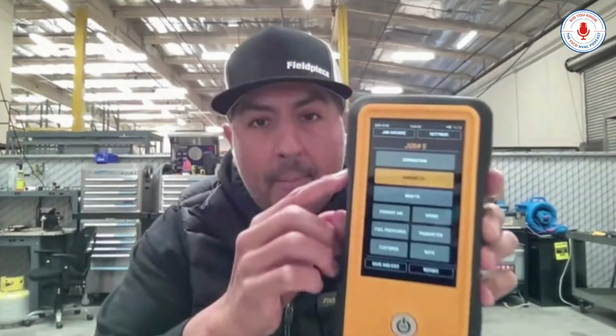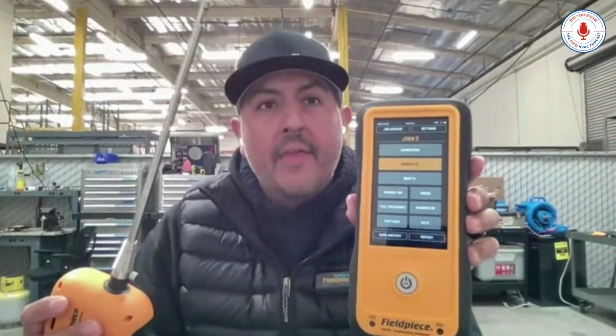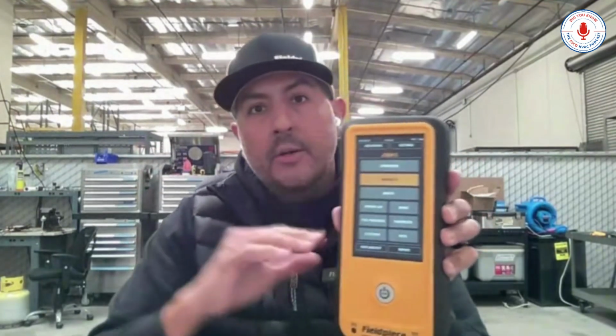Now I'm going to go back to the job menu, and now I am at the appliance under test. Okay, so fuel's out, ready to roll. However, there is one thing we should consider, and that is primary air, right? So, primary air is the air that is being fed to support the combustion process. For combustion, we need oxygen, we need fuel, and we need heat. Now, on a combustion analyzer, primary air is part of the combustion efficiency calculation that the tool performs.